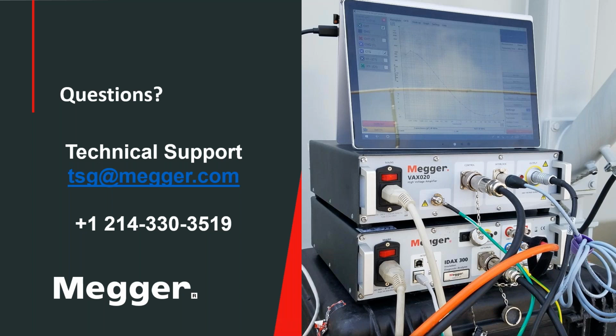For instance, if you are in the range of 20 degrees C or 30 degrees C, then you may only need to go up to 5 millihertz. But if you're working in a colder environment where the insulation temperature is in the range of 5 degrees C or 8 degrees C, then you may have to go to 2 millihertz or 1 millihertz.